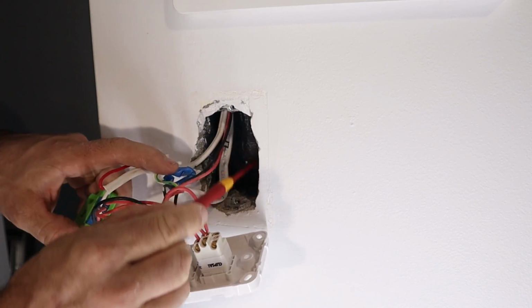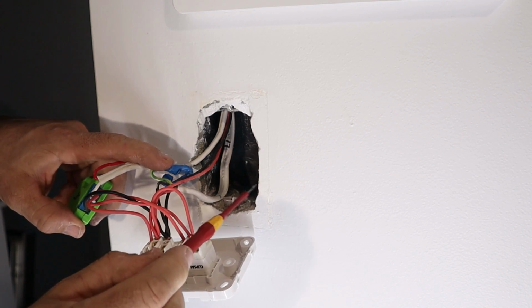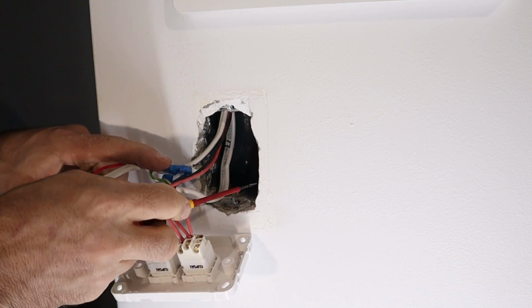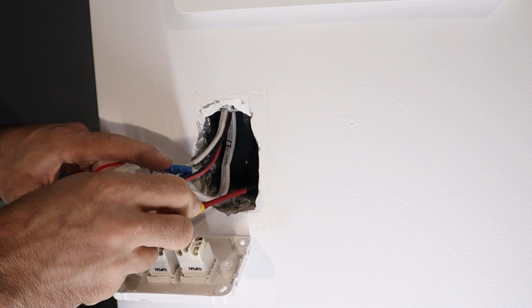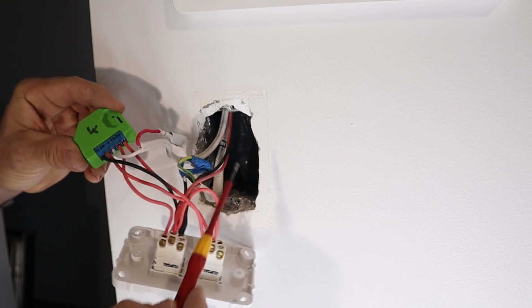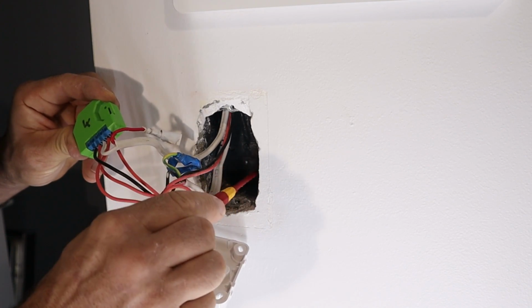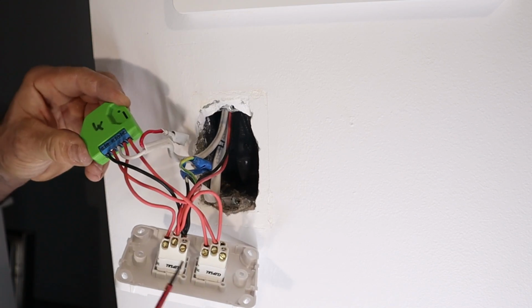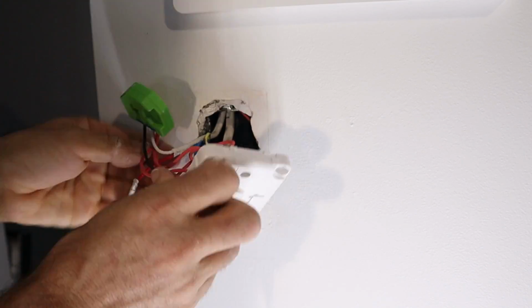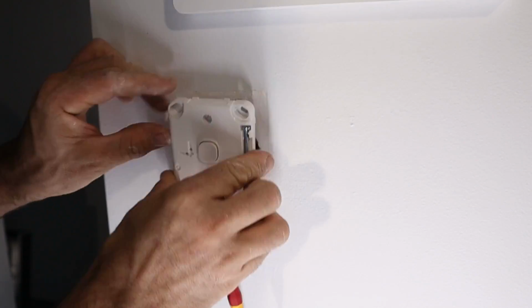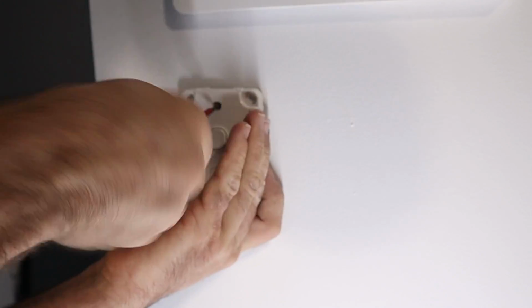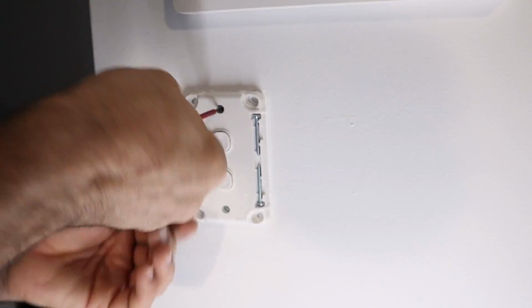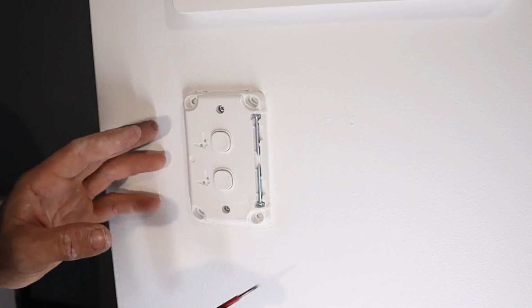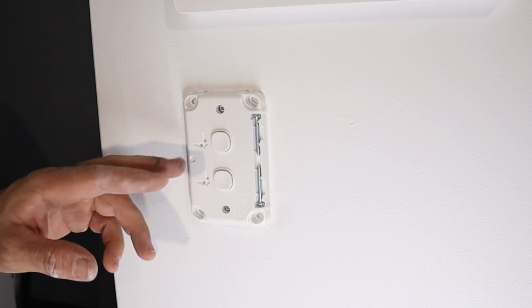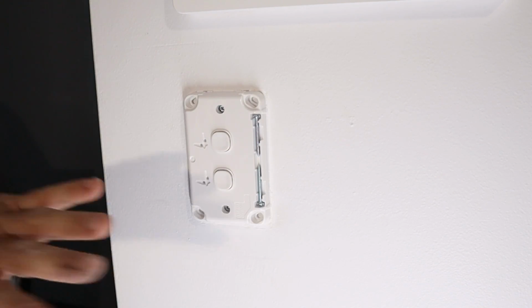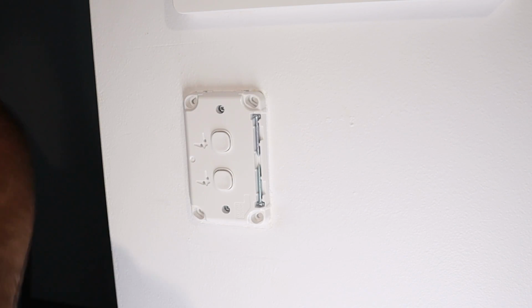These plastic wall boxes that are mounted in the brickwork, I've purposely put them back deeper than normal. So there's about 25 mil from the plaster to the switch box to make it easier to fit pucks back into the wall. But you can actually also get plastic wall boxes that are deeper than a standard, and it gives you more room to fit things like this in behind the switch box. So you can see how it can get tricky when you've got two switches, and it's almost impossible once you have three to fit everything back into the switch box.